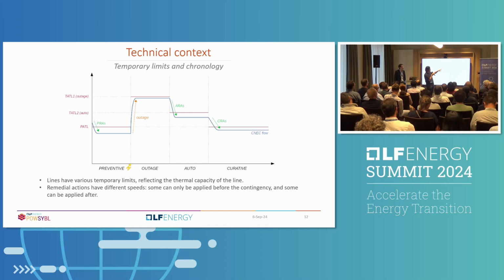Then to solve the second TATL, we have what we call automatic remedial actions. Some of you know them as SPS, maybe. These are actions which are not optimized and are not chosen by the operators. There are, for instance, PSTs on the network which will monitor the flow that goes via the PST, and it aims to keep that flow at a certain level. So if there's too much flow on the PST, it will automatically change tap to reduce the flow. These are very fast, which is why they are able to solve the second TATL.